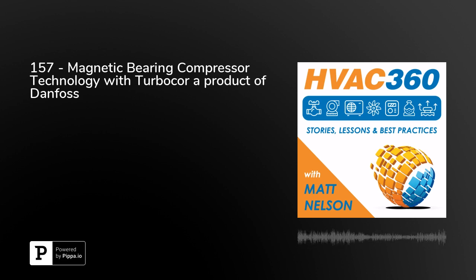And if you're considering having multiple compressors, the majority of OEMs use multiple compressors on their chillers. So 2, 3, 4 Turbocor compressors on a single chiller, and we've seen up to 12. That's one of the largest systems that we've seen. And when you have a centrifugal compressor and you're starting up multiple centrifugals at a time, they need to be able to generate enough pressure so that they can start up.